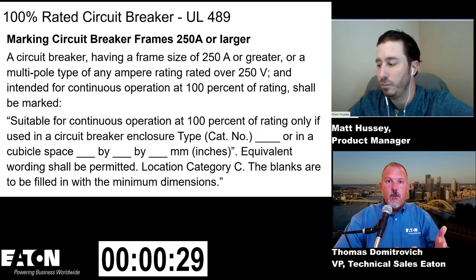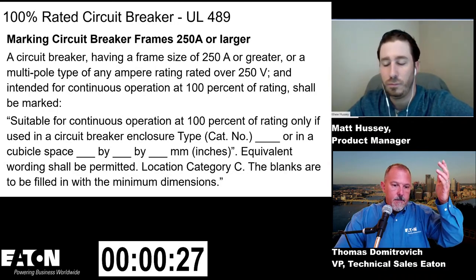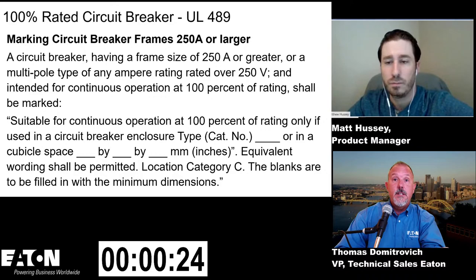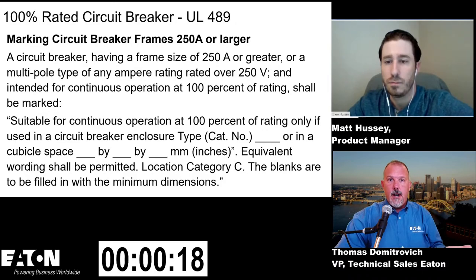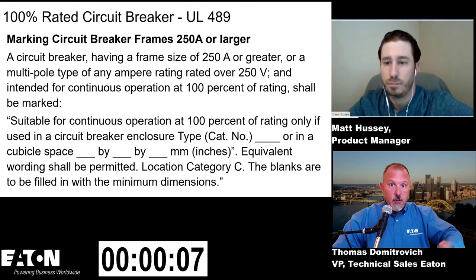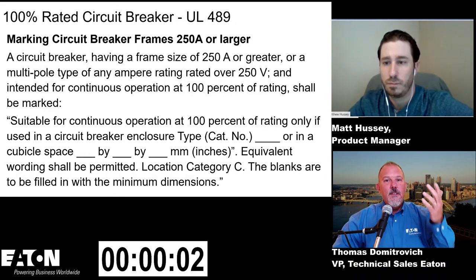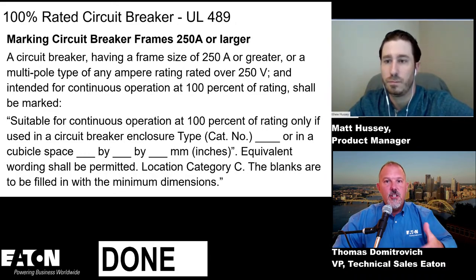So if I am out in the field and I did not include the details on my drawings when they sent them to the manufacturer for quoting the job, I'm going to quote an 80% rated piece of equipment unless something in the specification says it's 100% rated. If it's 100% rated, now I'm going to pick certain panel boards or certain circuit breakers. But if I shipped 80% and then you get it in the field, you have an 80% rated solution. I can't just change the circuit breaker. I may have to also change the panel board or the enclosure that it's in.